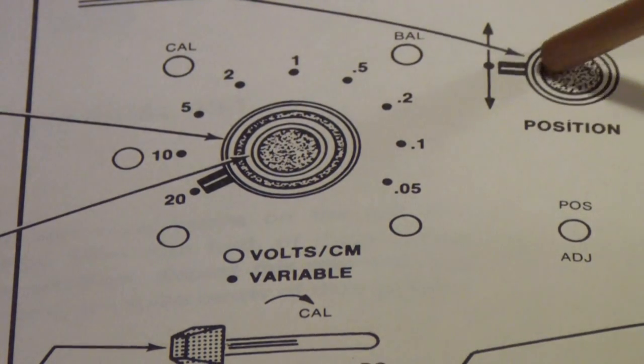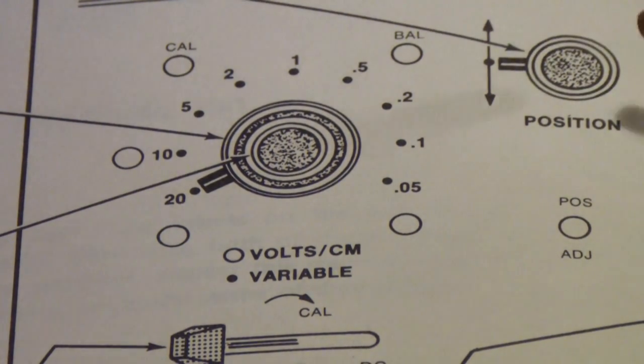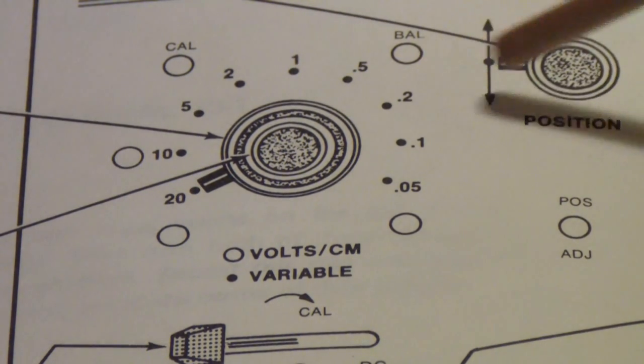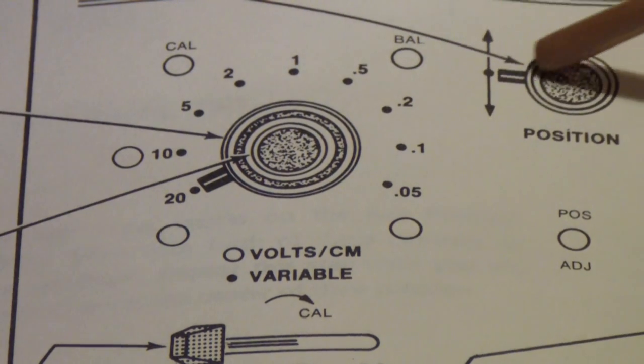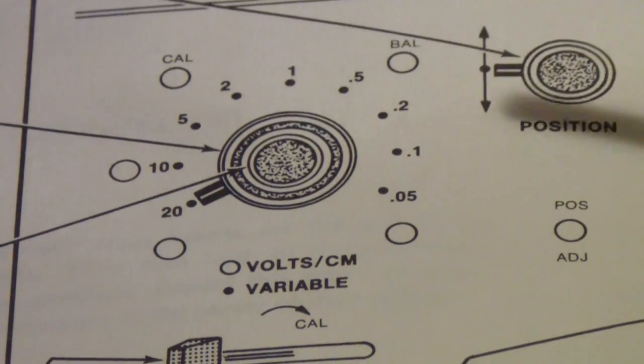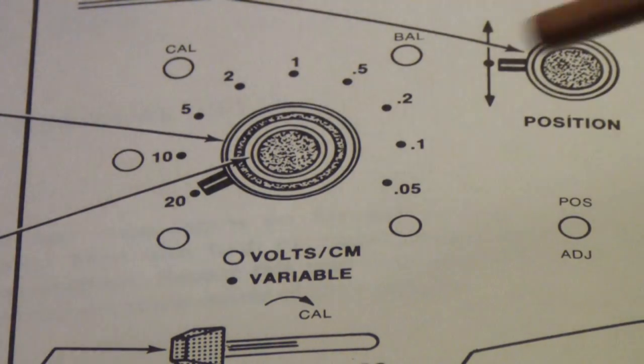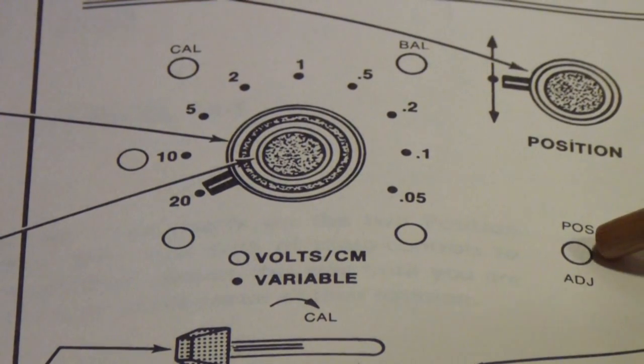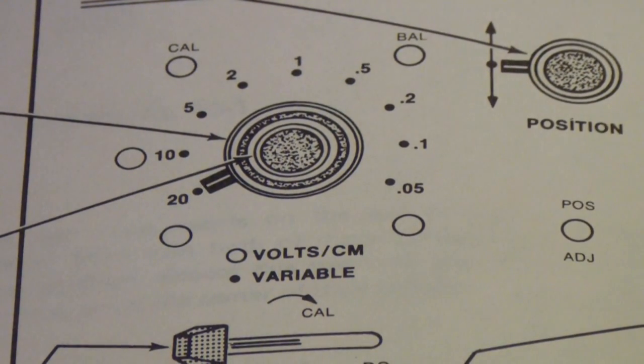For example, this one is to center the position adjust, that is, the position control for the vertical position. Over time it would drift, and if you set it back to the center of its range so that, for example, when you have this pointed at the nine o'clock position, that the trace would be in the middle of the screen, you would periodically have to move this adjustment with a screwdriver through the front panel.